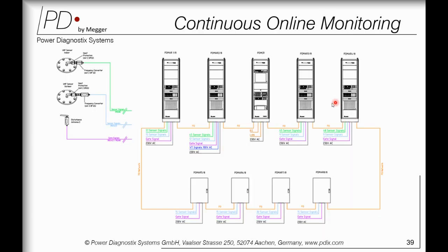So this is the complete setup of the online monitoring. This is your sensors, which are in the GIS. This is my disturbance antenna. This is my control rack. And as for the sensors, you may increase or decrease them. The acquisition rack, whether indoor or outdoor, is completely connected with the FO cable. So even if you have a break from any one side, the ring network always helps make sure that everything is communicating with each other.